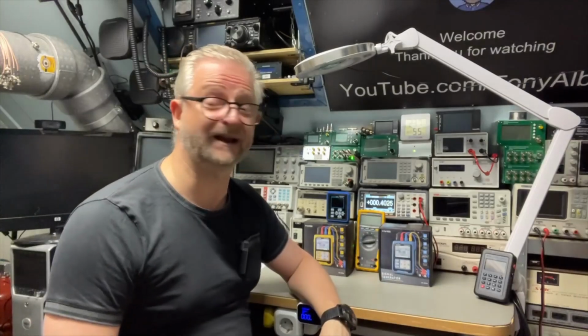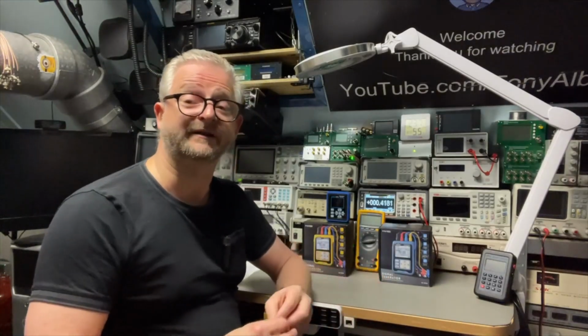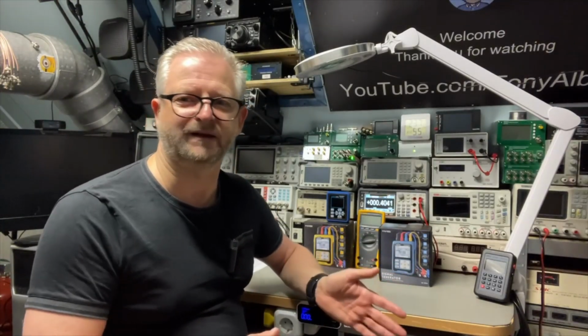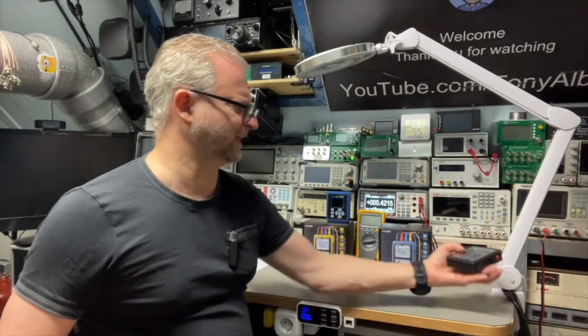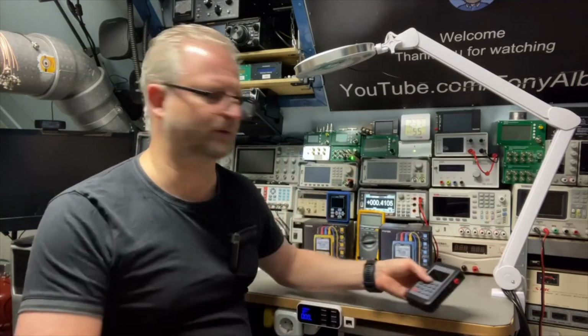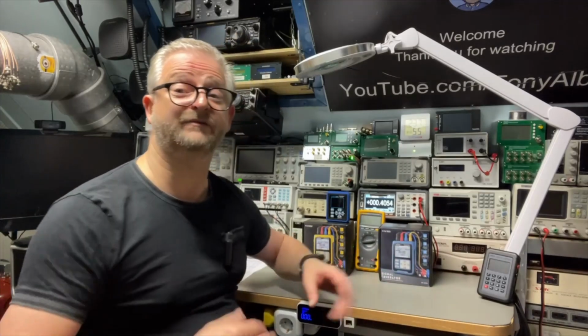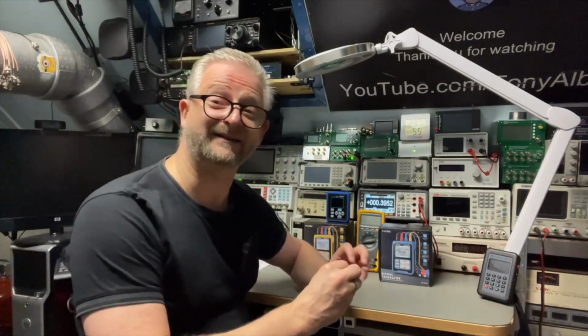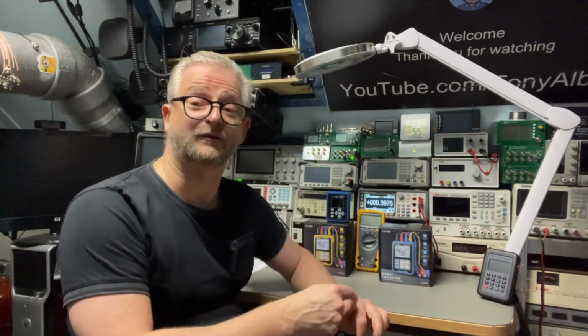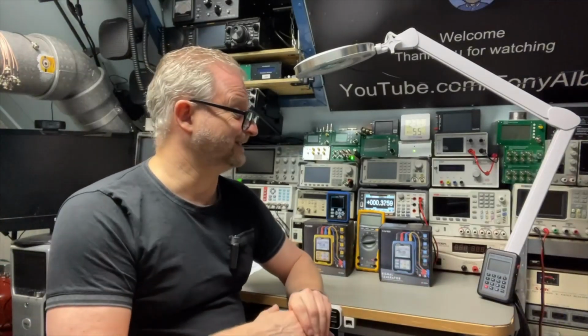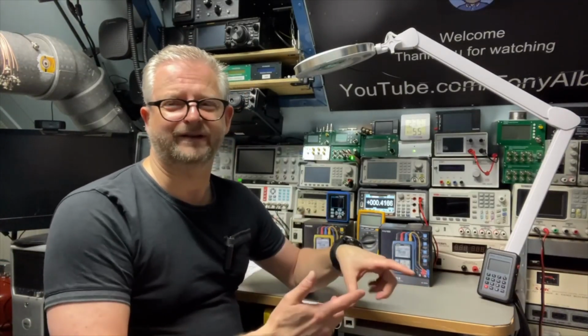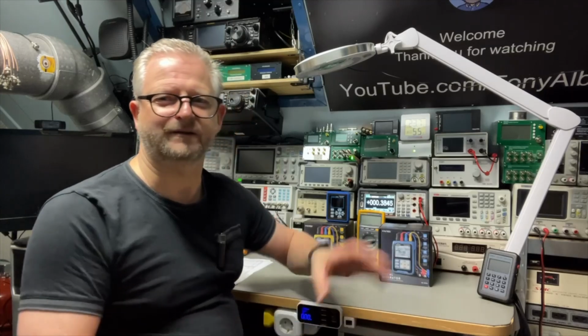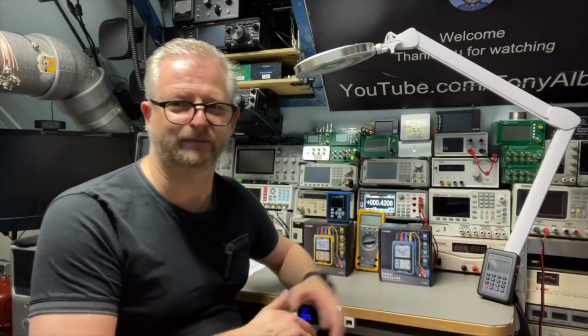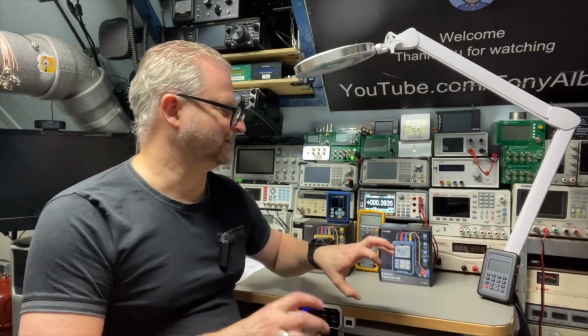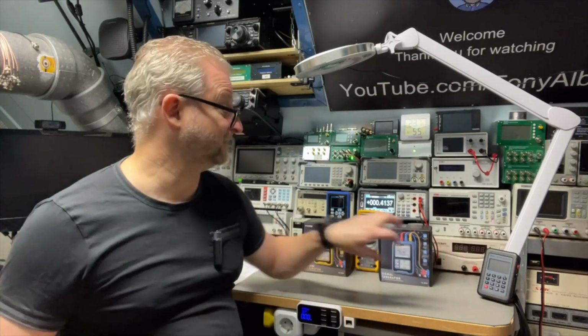But there are also more modern, advanced process calibrators that can emulate resistance, sometimes between 20 and 400 ohms, and with the LBO2 you can do a bit more, up to 2K. Some even have a small signal generator inside that produces square waves up to a few K. This is already the analog age, 0 to 10 volts, 4 to 20 milliamps, and later came digital, which was Modbus. So some even have that.